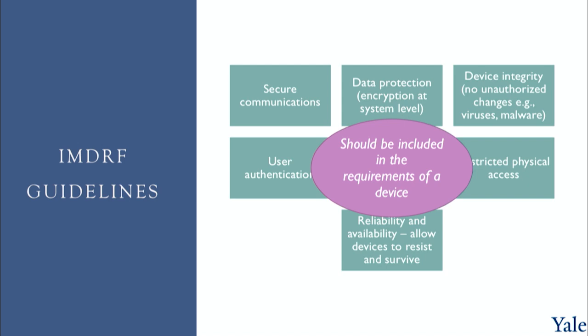And the guidelines suggest that all of those factors need to be accounted for in the requirements of the device. This is not, we design the device and then we worry about cybersecurity. No, cybersecurity needs to be factored in as we design a device. We'll have more to say about all of this in the context of the FDA regulations.